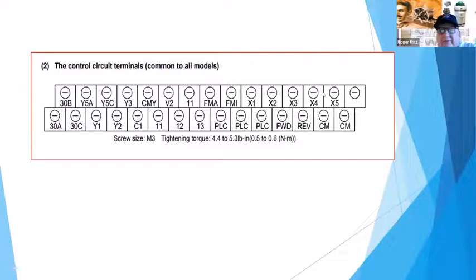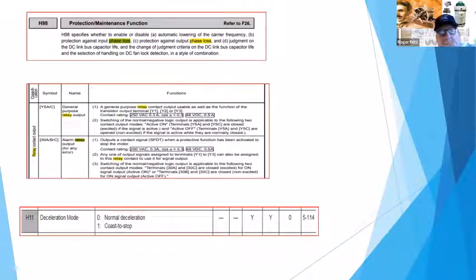And then you've got your various inputs here. So as you give a common signal between common and X1, you can program that to be the start function. Or you can go 3-wire, where you have a start, and then you have this going to the stop button, and you can have a 3-wire start-stop connection. And it's all programming. So again, go back to the basics and focus on that. So these are some various contact points. This one here is about phase loss.